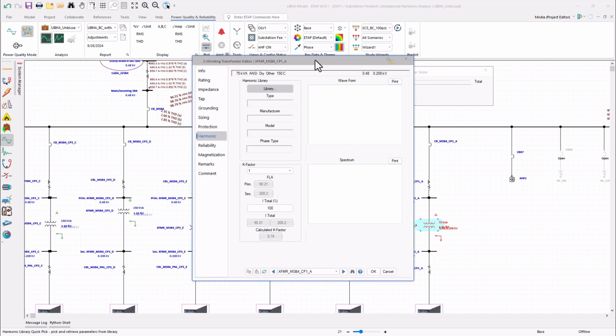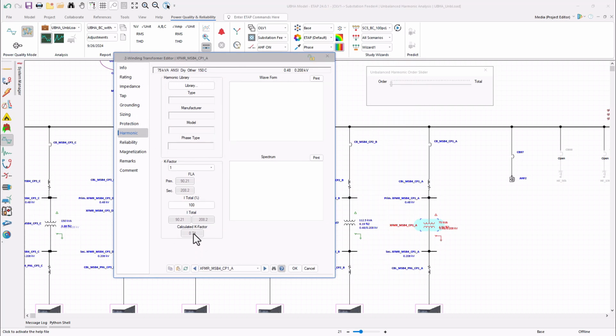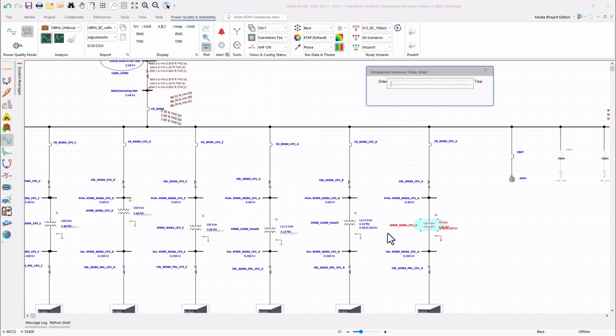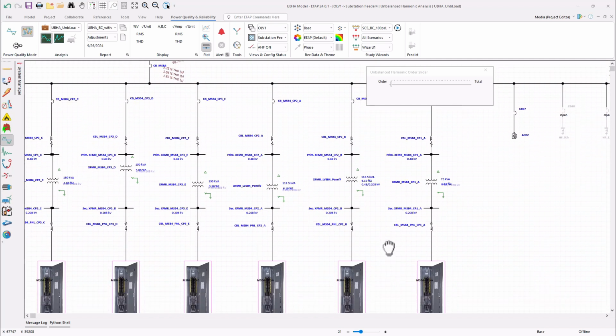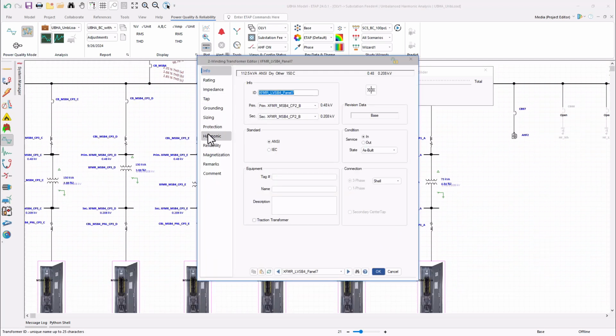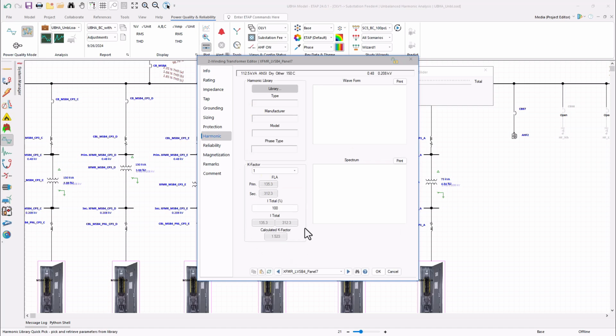In this case, for this transformer, calculated K factor is well within the rating of the transformer, but there are several other locations for the transformers connected to the panels where chargers are connected, such as this one, where calculated K factor due to the harmonic content is higher than the K rating of the transformer. Such cases might lead to excessive heat losses within the transformer, which would reduce the equipment operating life eventually. So for such scenarios, we have these evaluations done and recommendations offered to the client.